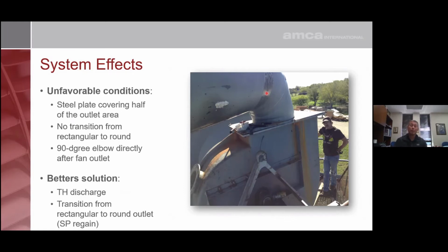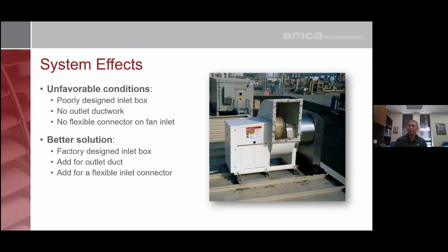Fan on top of a lab at an oil refinery. Very poor inlet box design, which we're going to see a little bit later in a video. Aspect ratio, depth compared to its width, not very good. Throws the air too high into the fan. Only utilizes the top half of the wheel to move air.